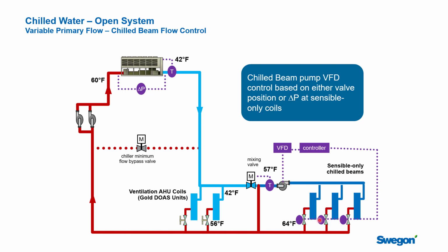So as these two-way valves open and the cooling load increases in the building, the valves open to service that load, the pressure would start to drop, the pumps would speed up to build the pressure back up and increase the flow rate out to the chilled beams. Reverse is true. As the load drops off, these valves start to close at the control zones, and then what happens is the pressure starts to build up. That signal comes back and tells the VFD to slow the pumps down. An alternative way to do this would be if you had position indicators through a building automation system of all your valve positions. This is actually a more advanced and a more energy efficient way to do it.